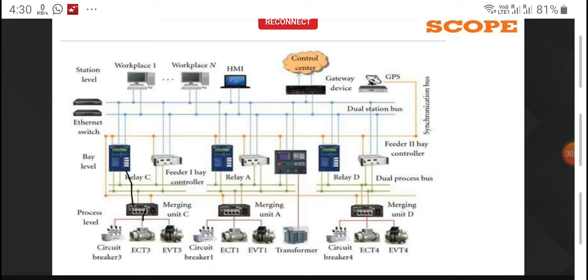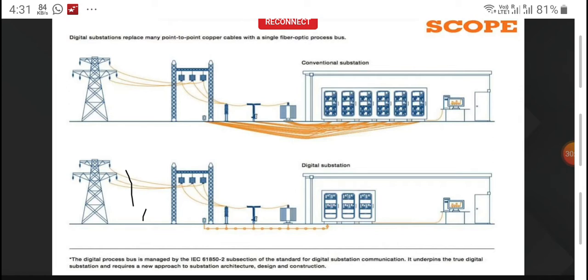That is the normal way: the 61850 9-2 and 8-1 protocols are used, and you can monitor. This is like what we are using presently, and you are going to use the same at the bay level and station level. But the process level is going to change with the optical fiber. This is mostly what the digital substation is about, and this is some differentiation between the conventional, SAS-based substation and the digital substation.